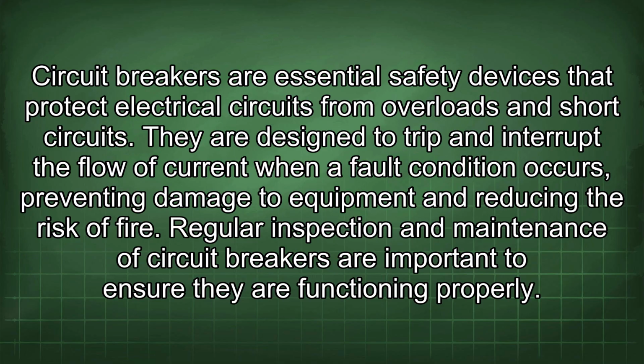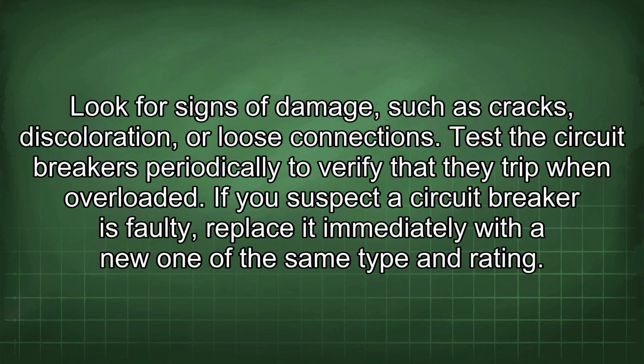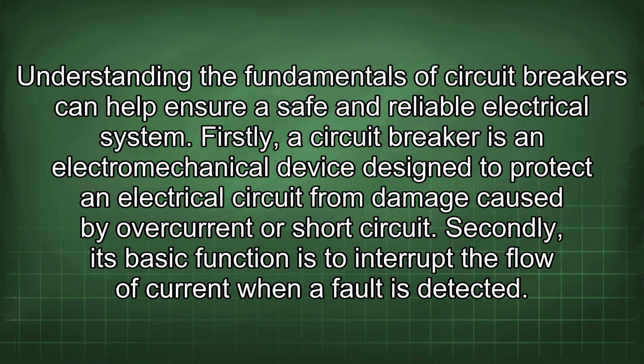Regular inspection and maintenance of circuit breakers are important to ensure they are functioning properly. Look for signs of damage, such as cracks, discoloration, or loose connections. Test the circuit breakers periodically to verify that they trip when overloaded. If you suspect a circuit breaker is faulty, replace it immediately with a new one of the same type and rating. Understanding the fundamentals of circuit breakers can help ensure a safe and reliable electrical system.